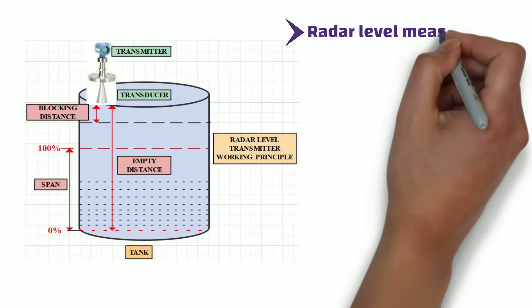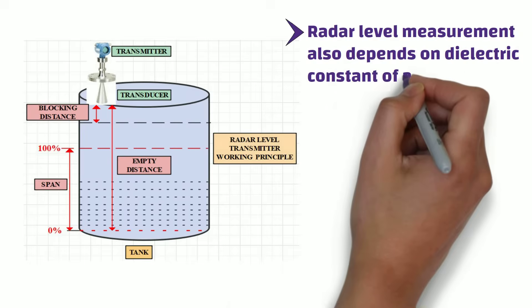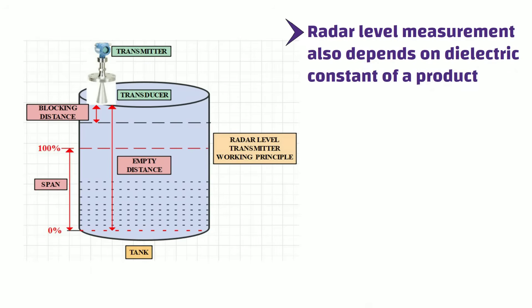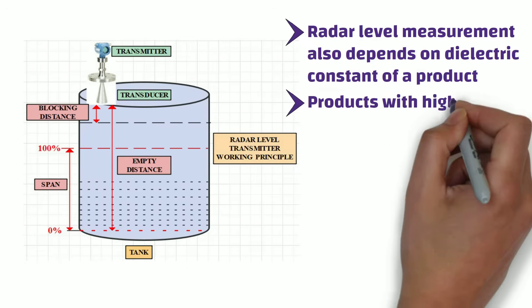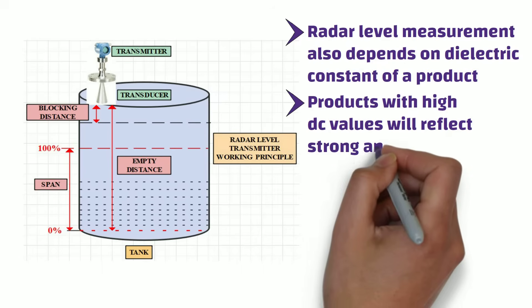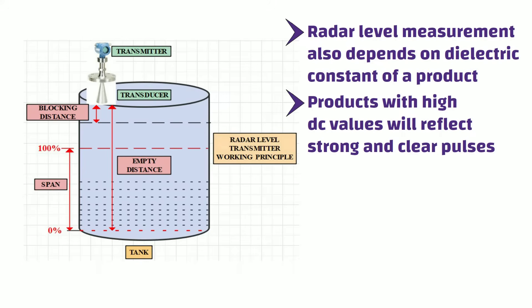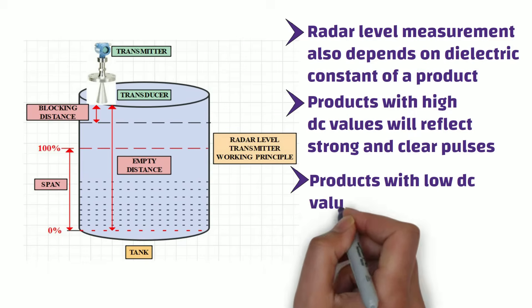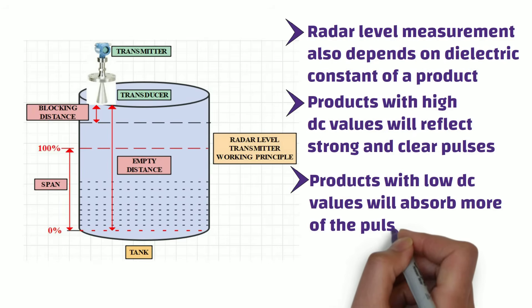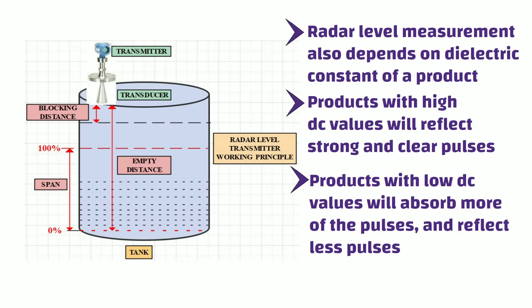Radar level measurement also depends on the dielectric constant of a product, as it has a direct impact on the quality of reflections. Products with high dielectric constant values will reflect strong and clear pulses, making them excellent for level measurement. On the flip side, products with low dielectric constant values absorb more of the pulse and reflect less, so radar level instruments do not give accurate level measurement for these products.